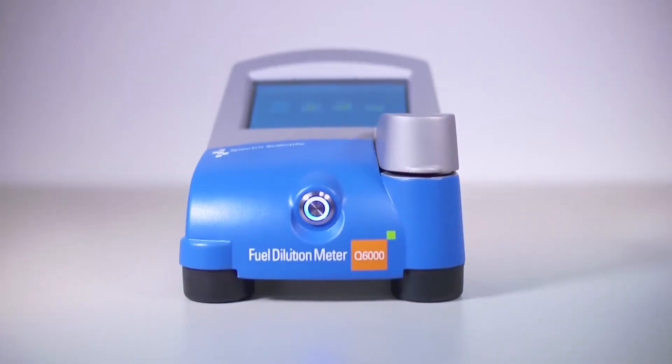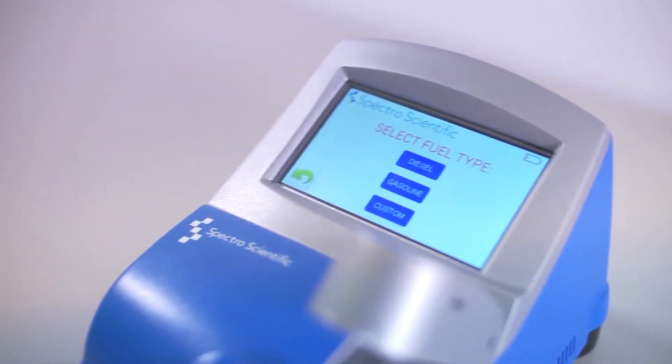The Q6000 is the next generation fuel dilution meter. The technology was originally developed in conjunction with the US Navy many years ago which focused on a sonar acoustic wave sensor as a quick and easy way to measure excess fuel dilution in crankcase engine oils in the field.